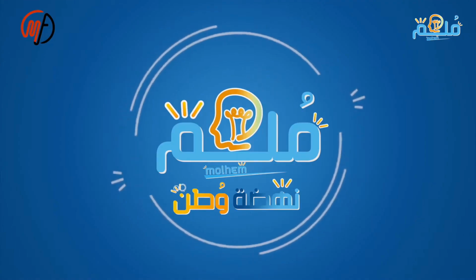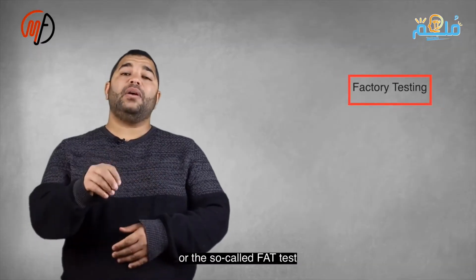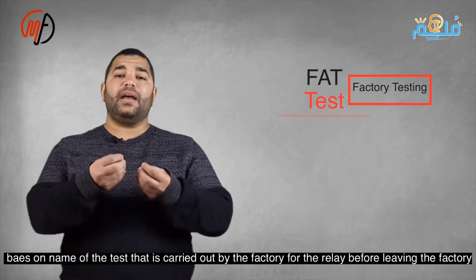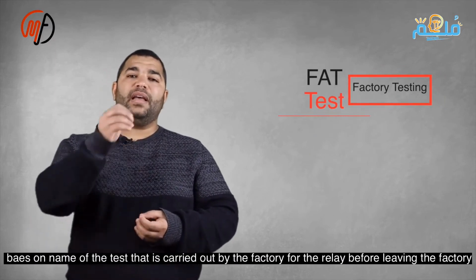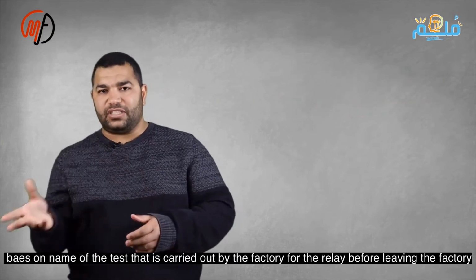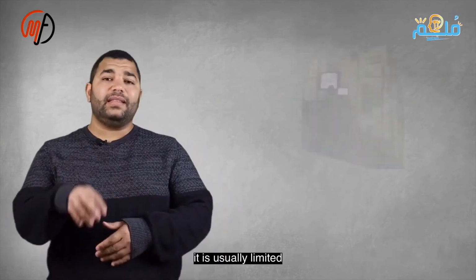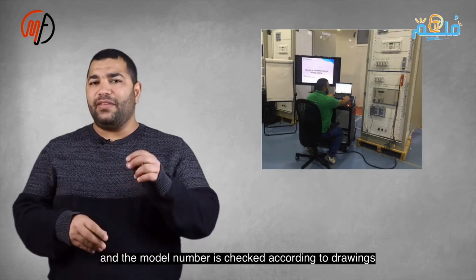Factory testing occurs before a relay leaves the factory. Tests focus on verifying model numbers, checking connections, and components. An advanced relay's factory test may last under an hour, while on-site testing can take 4 to 5 days. Typically, end users send engineers to witness these tests and ensure safety before the relay leaves the factory.